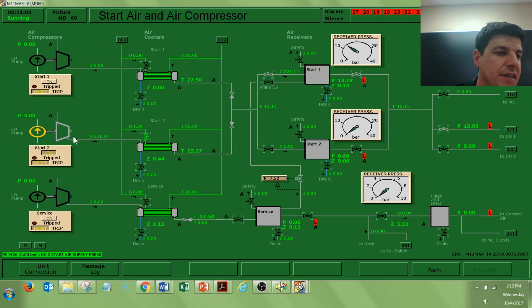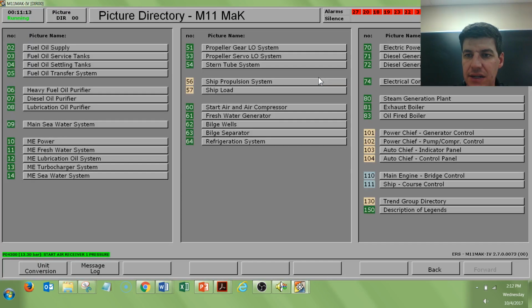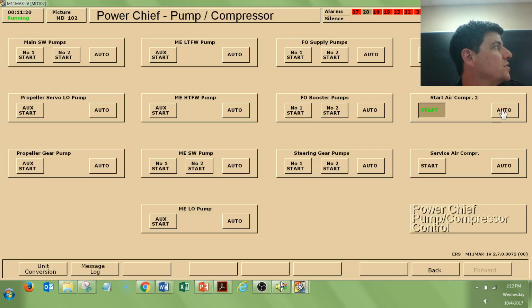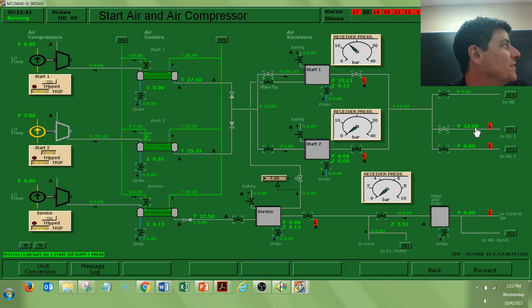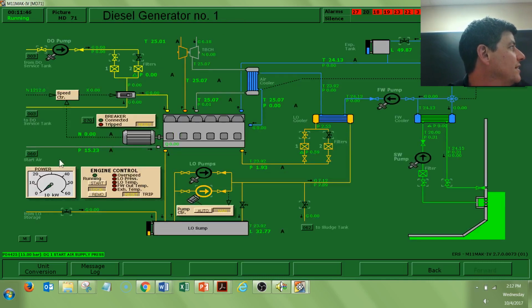My start air, if I leave this guy on, it will eventually get to 15, but it will keep going and overpressurize this tank. So what you can do to avoid that is use your automated controls at 102, and I could turn my start air compressor number 2 into auto. Oh, never mind. It has to get to 15 before you can. No, it is relying on me having electricity first, so that isn't off of the main or the emergency generator bank. So, sorry, we'll backtrack. There, oh, perfect, 15 bar. I was just stalling. All right, start my generator.